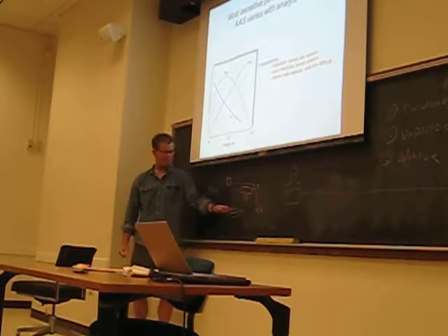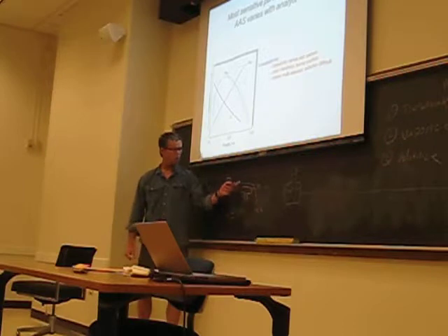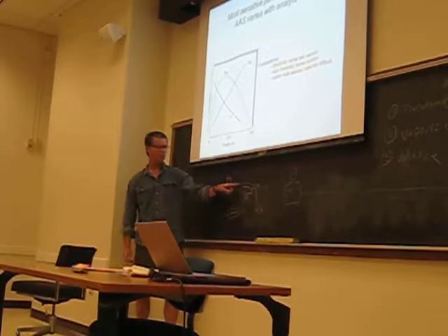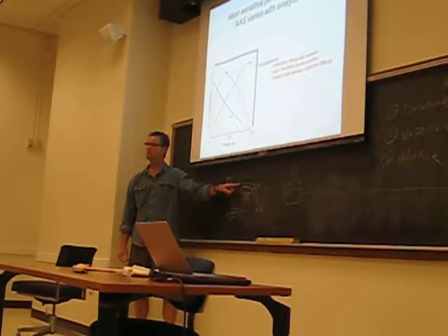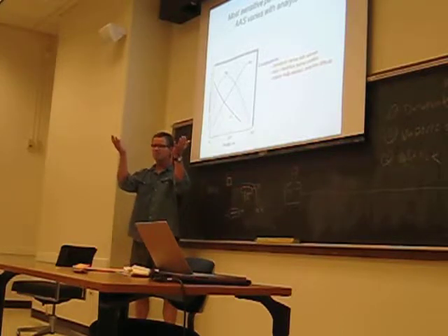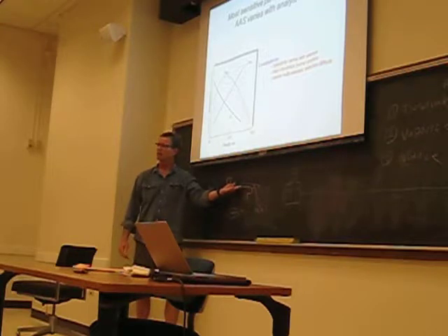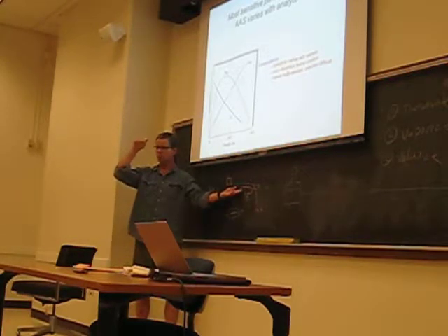And then once that's lined up that way, once you start the flame and you're aspirating some solution, what the TAs should have done is slowly raise that until this burner head starts to occlude the light beam, and then you get very large absorbances because it's blocking the light beam. And then you start to lower it, and you keep lowering it, and you're watching as you're aspirating your solution with copper in it, and you maximize the absorbance based on that.